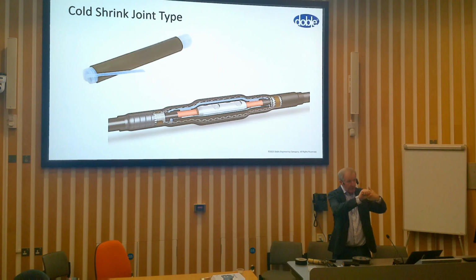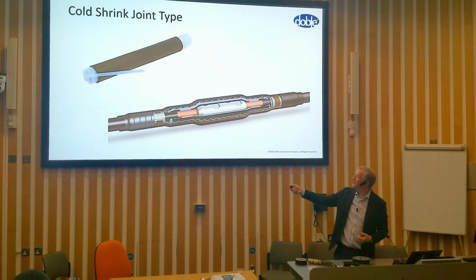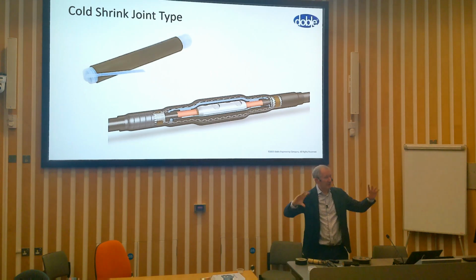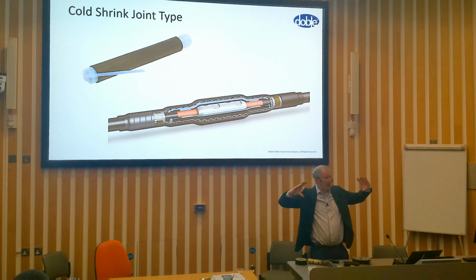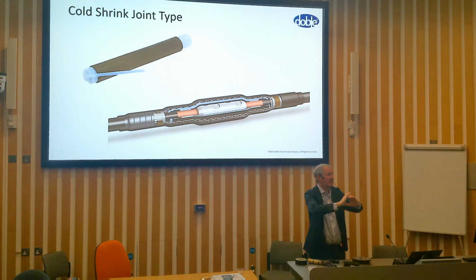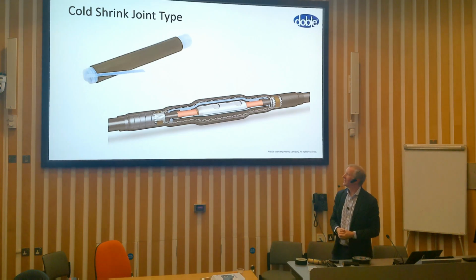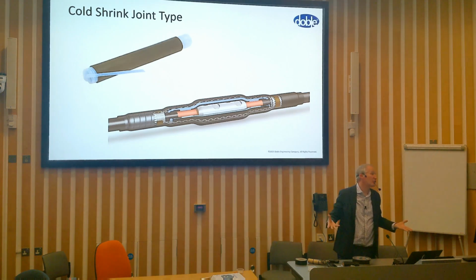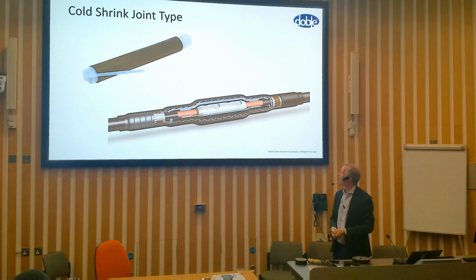You slide it over the cable, and when you want to take it off or compress it down, the bit that sticks out the end is actually connected to the far end. As you pull it, the spring basically pulls through, and the whole thing shrinks down and snaps into place. It's quite clever - that's why it's called cold shrink, because they don't actually have to do anything with it.